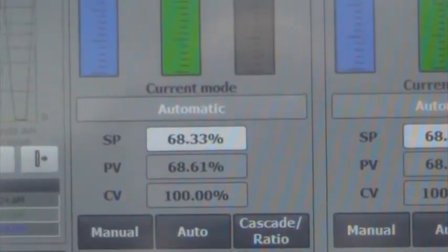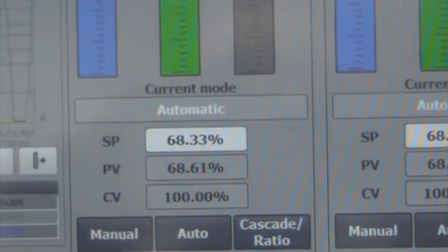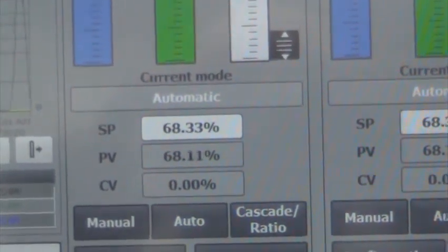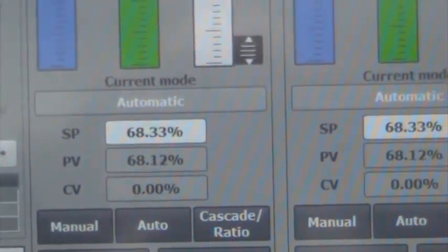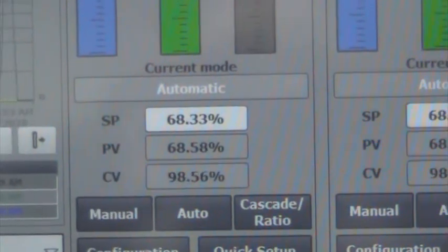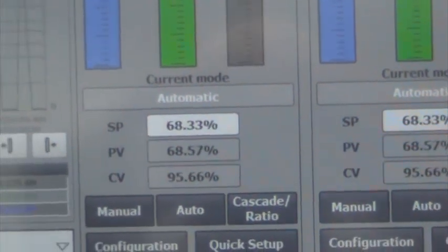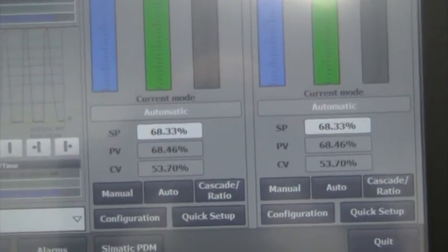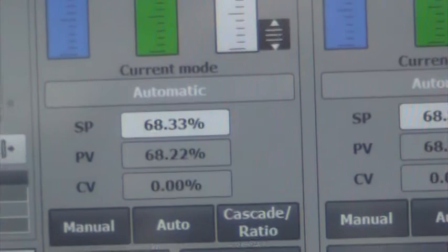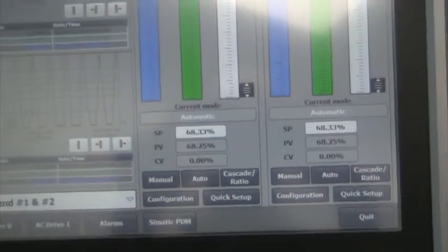The control is pretty good. If you look, the set point and the process variable are very close to each other. The only problem is that the controller is working very, very hard. The pneumatic controller is working very hard. So almost an on-off control. Not exactly an on-off, but almost an on-off control. So this is okay as a controller, and this is automatic control, obviously, because I'm not controlling the flow of water. It's automatic control, but the problem is the big fluctuations.